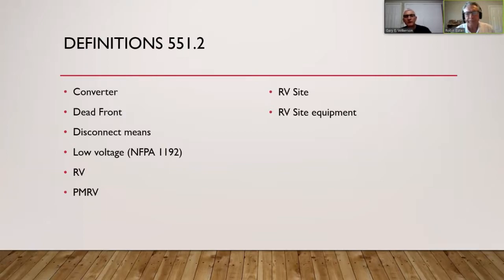A dead front is something that protects the person from being near or close to energized parts. So if you looked at Article 100 in the definitions of the code book, it talks about a dead front, and the dead front is without live parts being exposed to a person on the operating side of the equipment. So they want to make sure that there's a metal cover in that panel, that when you open the cover, there's still another cover where your hands cannot touch energized parts in the panel.